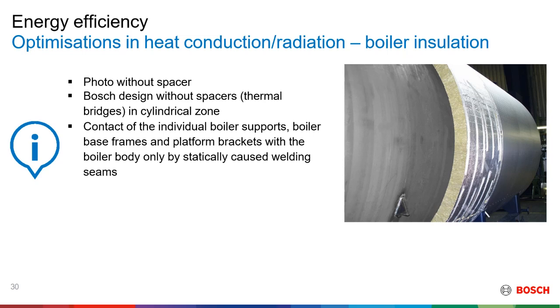On the slide, you have a boiler which has not been cladded yet. As you can see, the cladding there is around 100 mm. And you have a small contact point where the boiler shell gets in contact with the boiler frame. Just by reducing the amount of contact the boiler shell has with the frame, you reduce the surface of heat transfer or heat loss. Then the second part is having good enough cladding. You reduce the amount of conduction losses from the boiler shell.